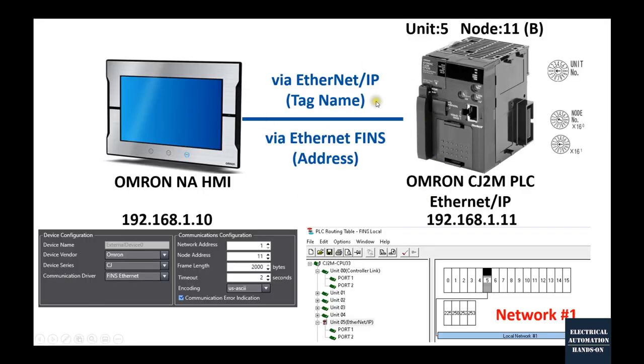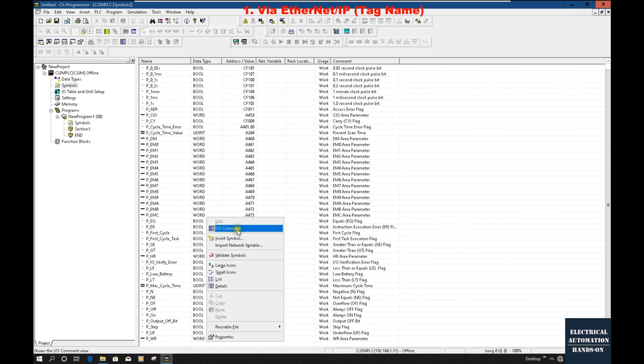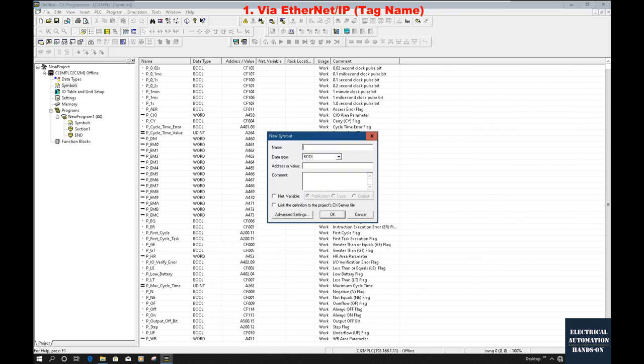Now let's talk about settings that allow the HMI to communicate with PLC tags. The key setting comes from the symbols section. First, let's talk about how to set up the connection using EtherNet/IP with tag names. If you are going to use EtherNet/IP, you can create W address or H address symbols.